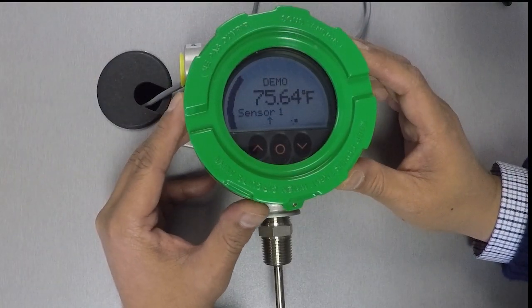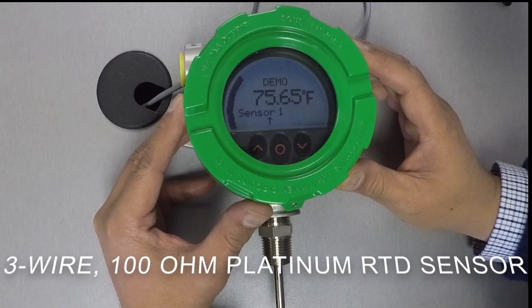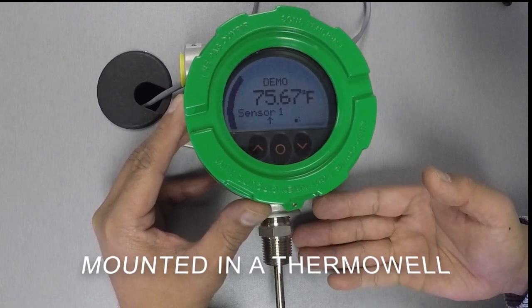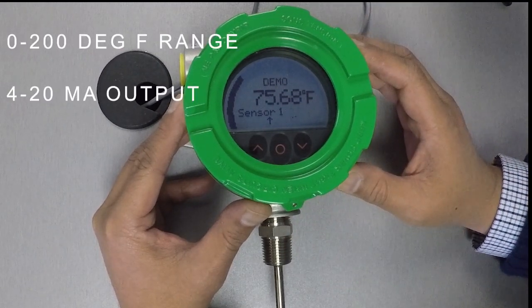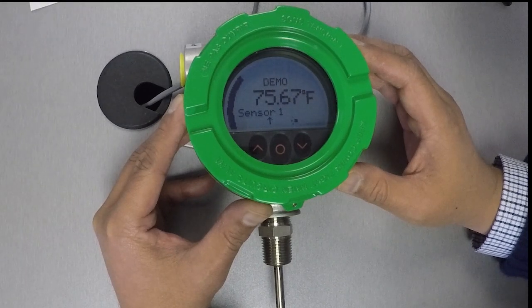Alright, so in our demo unit here, the temperature sensor we have connected to it is a 3-wire, 100-ohm platinum RTD sensor mounted in a thermowell. Let's go ahead and configure the instrument to have a 0–200 degree Fahrenheit measurement range with a 4–20 milliamp output that linearly represents that range. We'll do this by going into the unit's basic configuration.